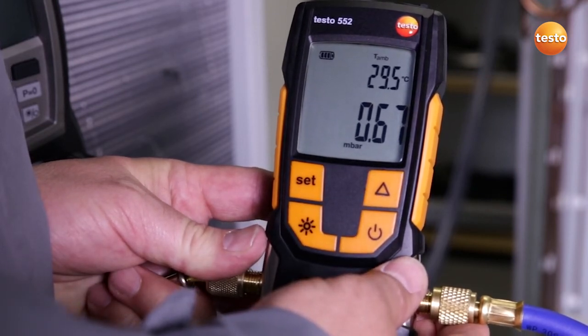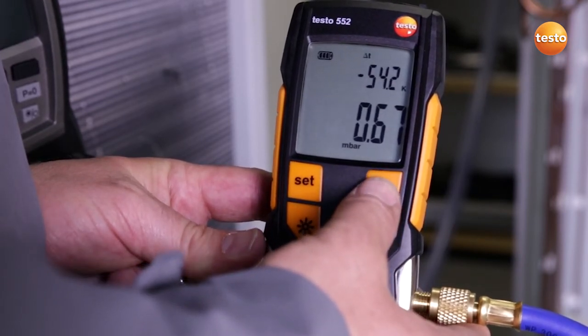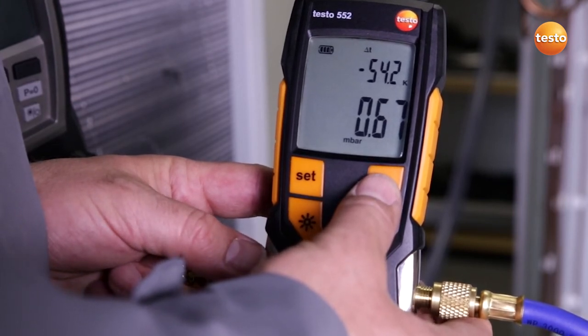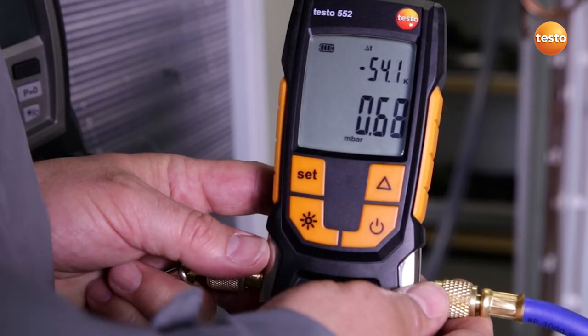That corresponds to an evaporation temperature of the enclosed water of minus 24.7 degrees Celsius. Since we have an ambient temperature of 29.5 Celsius at the moment, this means that with a difference of exactly 54.2 Kelvin, we have enough difference to evaporate all humidity in the plant system. The evacuation procedure is finished and the system is ready to be filled.